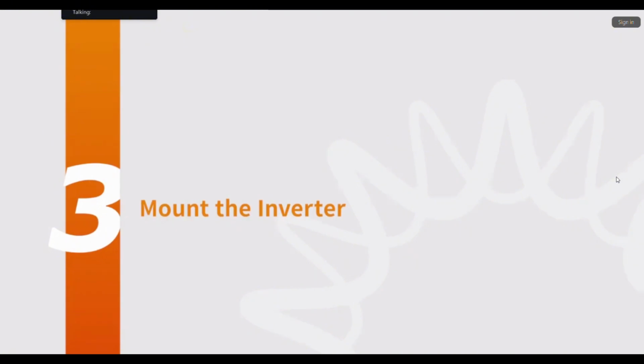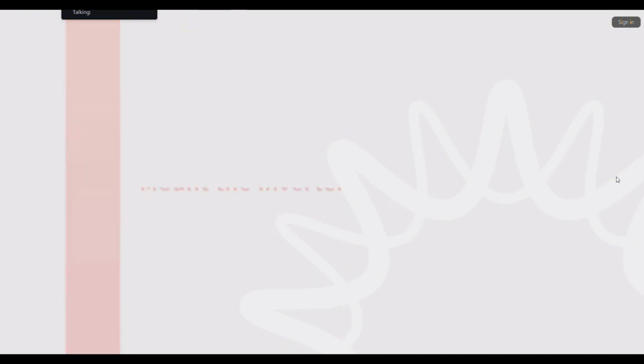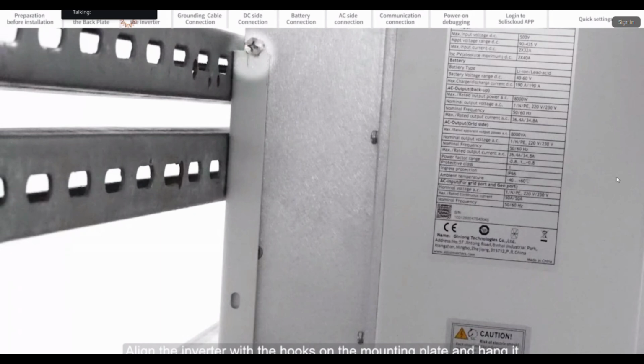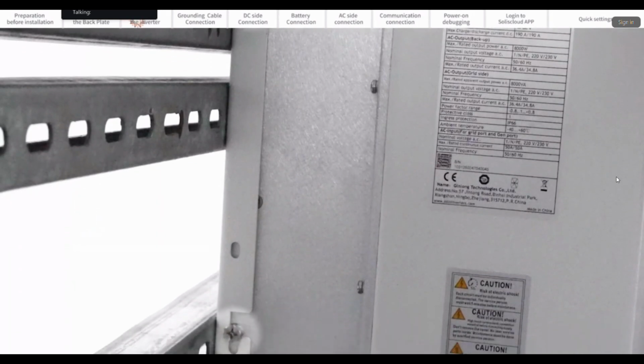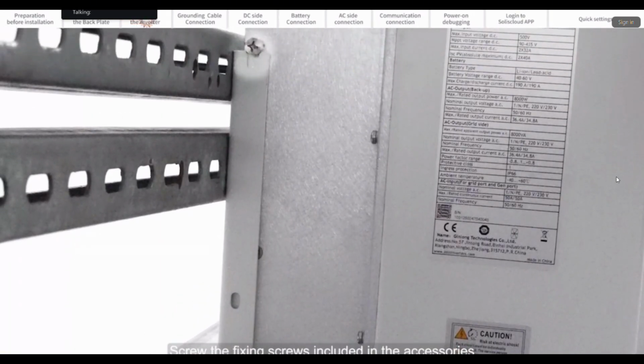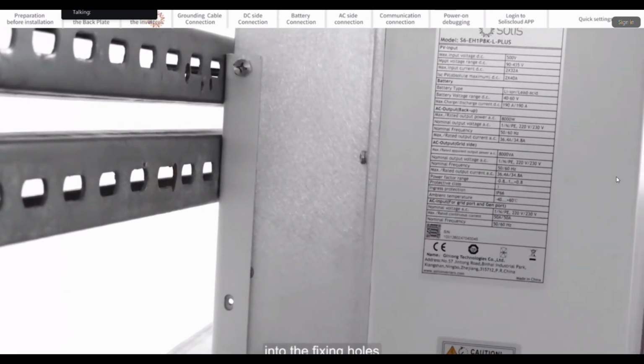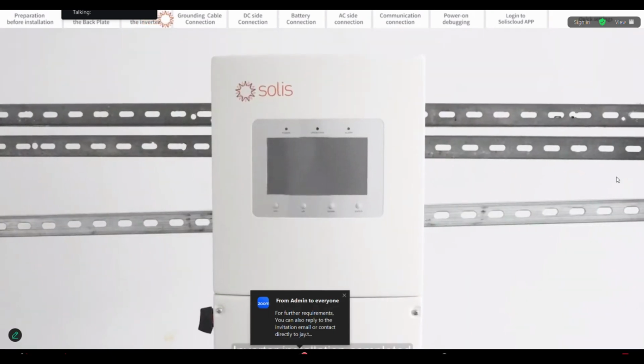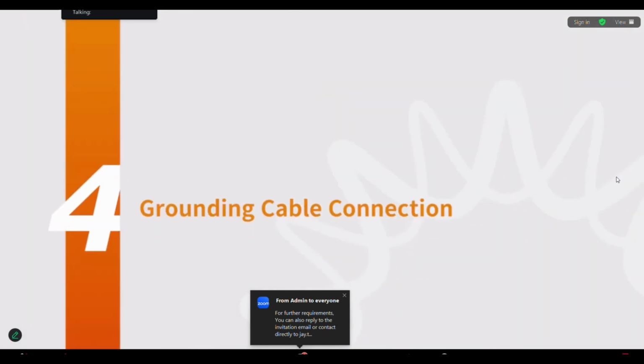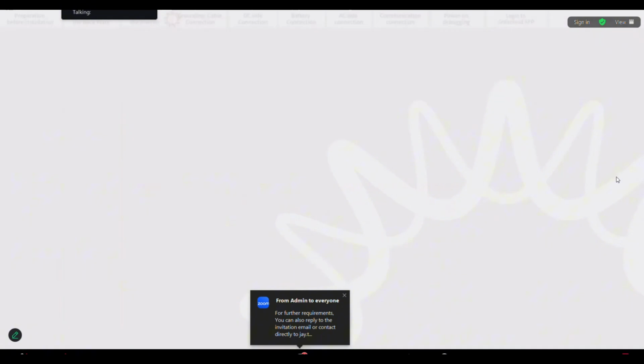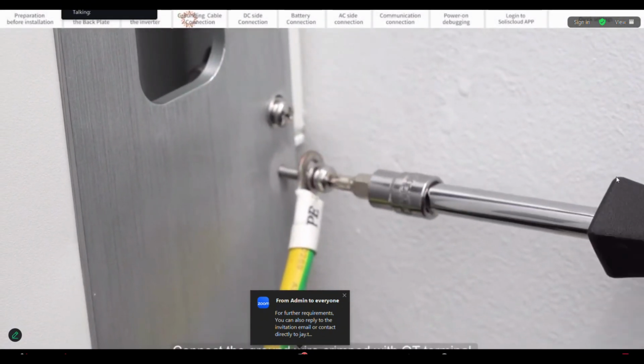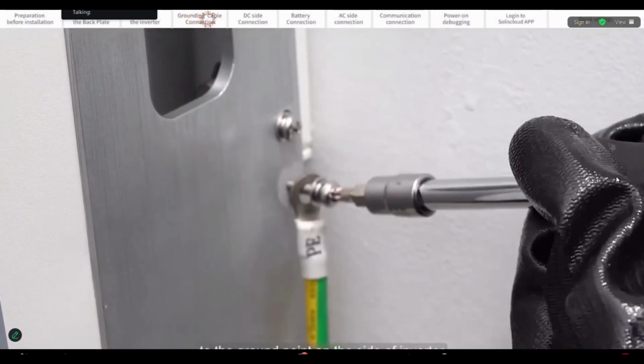Part 3. Mount the inverter. Align the inverter with the hooks on the mounting plate and hang it. Screw the fixing screws included in the accessory bags into the fixing holes. The inverter installation is complete. Part 4. Grounding cable connection. Connect the grounding wire crimped with OT terminal to the ground point on the side of the inverter.